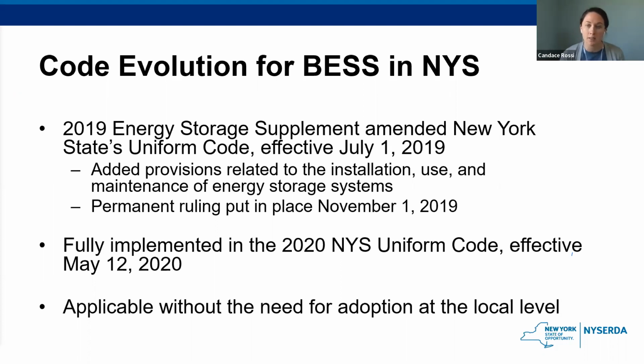So this amendment updated the energy storage fire safety requirements from the draft 2021 codes, and it is likely the most stringent code in place across the country. The Uniform Code is the law statewide outside of New York City, which has its own codes. This supplement has been incorporated into the latest code cycle as of May 12th, 2020. So it's fully incorporated into the Uniform Code, and this presentation covers the new requirements at a high level, but does not convey every detail or nuance. So always refer to the Uniform Code for complete system requirements.